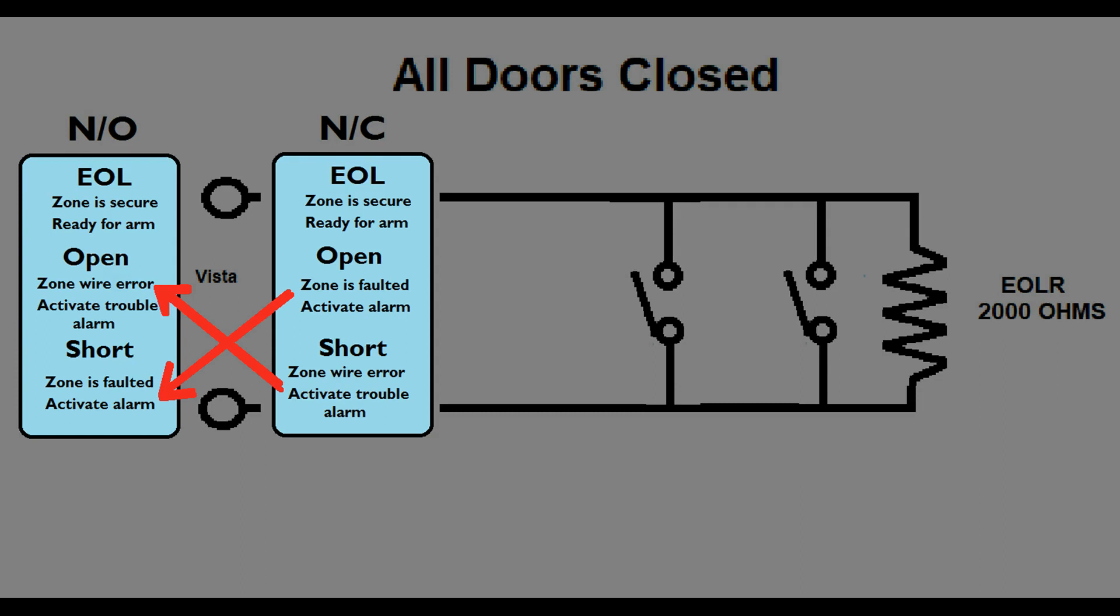Here's the difference in how they respond. With a normally closed sensor, an open activated your alarm system. With the normally open sensor, a short will activate your alarm. And likewise, on normally closed sensors, a short is a problem with the wiring. Normally open sensors see an open as a problem with wiring. Let's look at some examples.